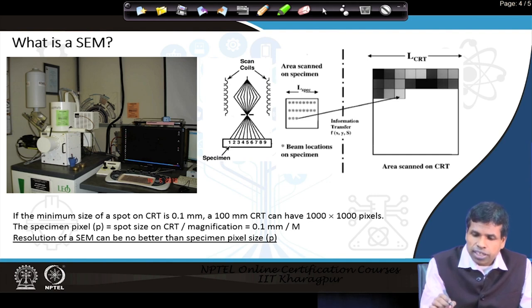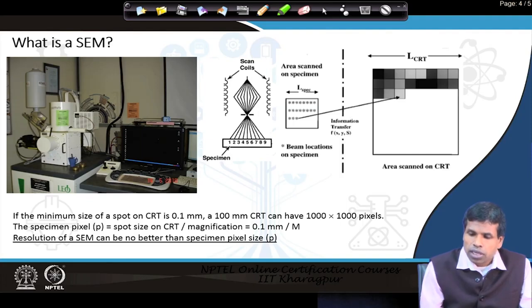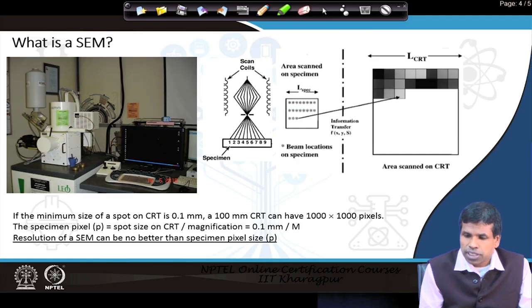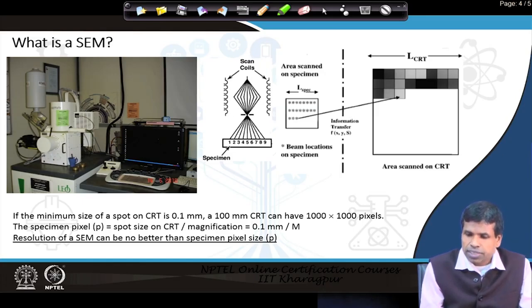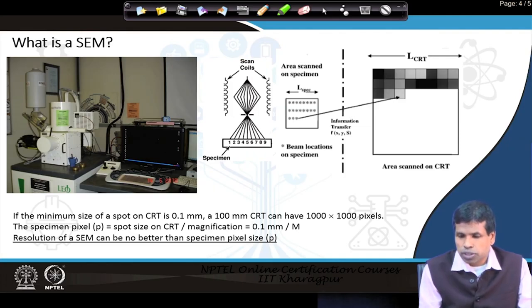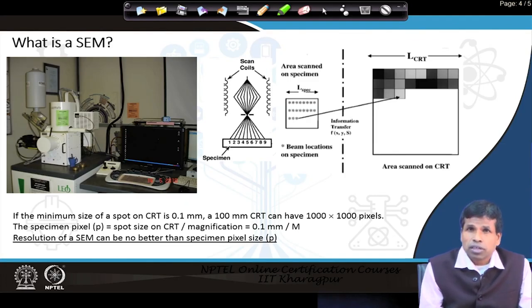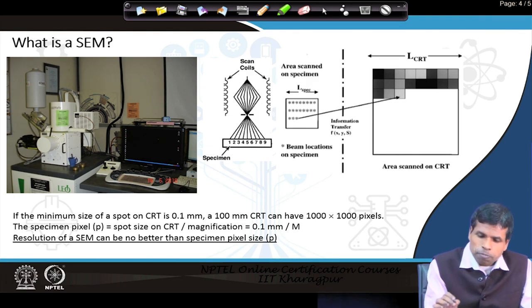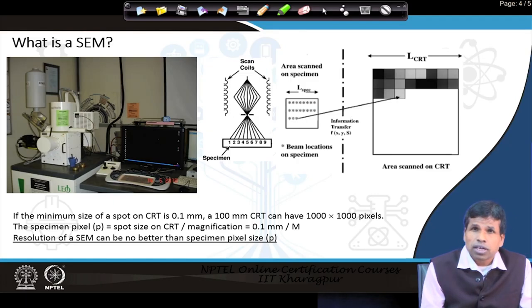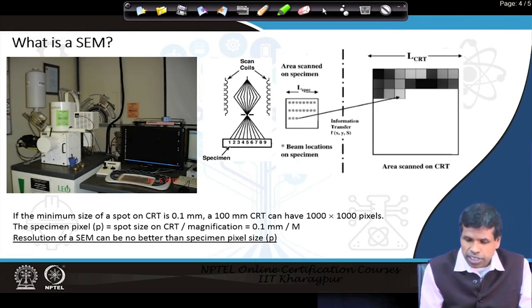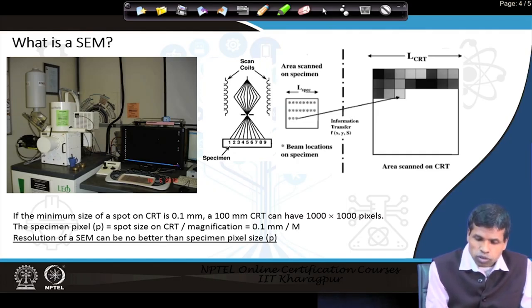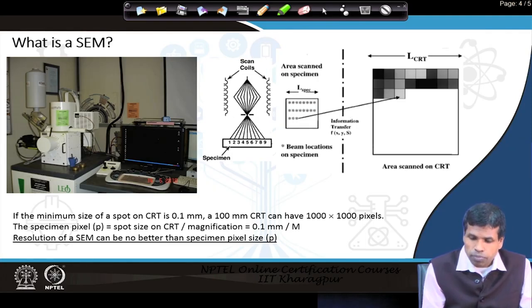The electron beam scans across the surface, secondary electrons generated from each point of the specimen are collected by the detector, and passed to the image processing system to produce an image on screen. If the minimum spot size on the CRT screen is 0.1 mm, then a 100 mm CRT will have a 1000 × 1000 pixel grid. The specimen pixel — the smallest size on the specimen where the electron beam is incident — equals the CRT spot size divided by magnification: specimen pixel = 0.1 mm / M.